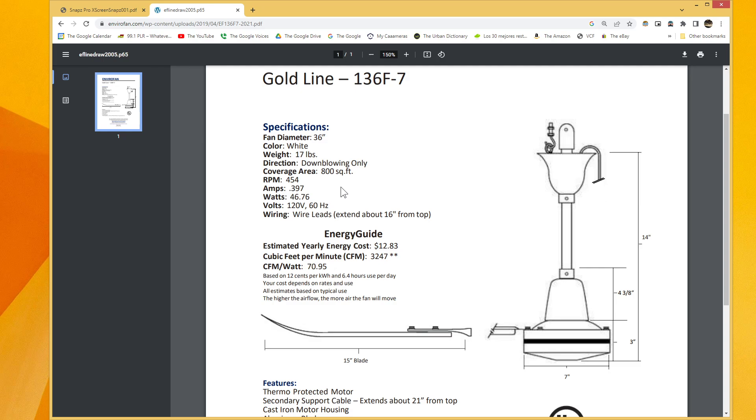This is the detailed specifications for the 136F for comparison purposes. The 56 inch models, a lot of them were rated in the 7,000 range, which I think is spot on. That seems very reasonable. And this 36 inch one is rated for 3,247 CFM, which I also think is spot on. I've used other 32, 36 inch fans with similar ratings, and they feel about the same.